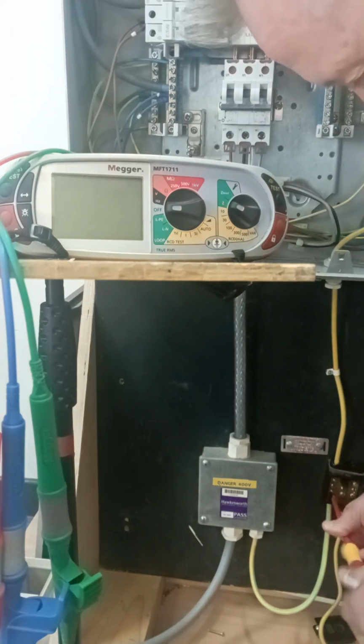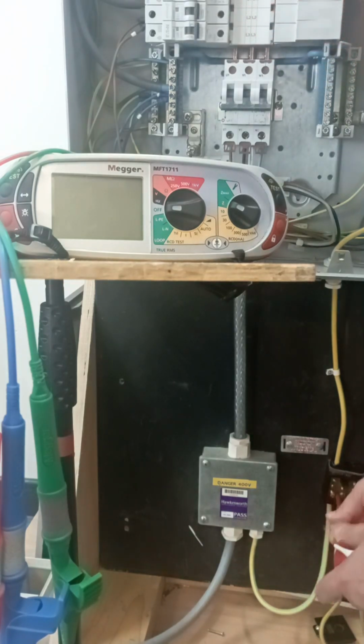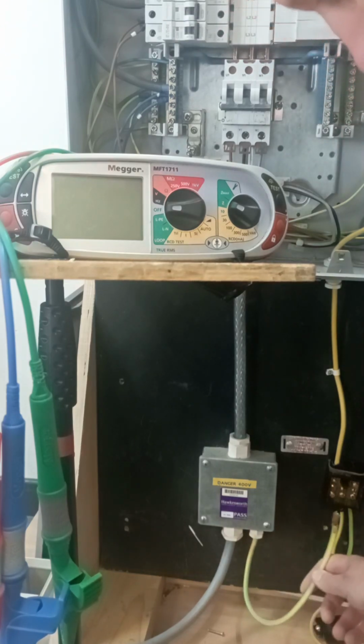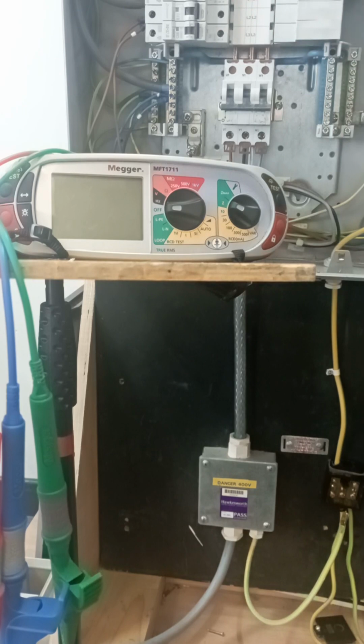disconnect the earthing conductor from the main earthing terminal. So that earthing conductor gets disconnected. Now you can use a tool to remove that. I'm standing here on a big mat, I'm not touching any other exposed or extraneous conductive parts. The cable's insulated, so I'm quite comfortable disconnecting that, but you might need gauntlets, you might need pliers, things like that to remove it, depending on what your risk assessment says.